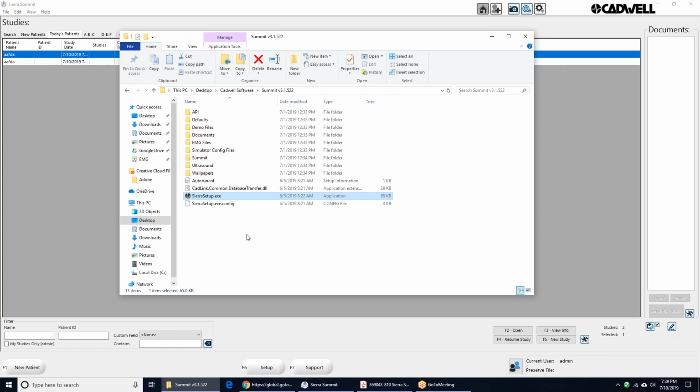The third scenario is a customer who is upgrading to 3.1 and they want to start using NCS Plus instead of NCV, and maybe also EMG Plus if they've been using EMG prior. For that customer, you really have to plan on a whole new in-service because you're going to be training them on the new software. You're probably going to be setting up test setups for them, maybe setting up new reference values in NCS Plus. So it's a pretty comprehensive upgrade.